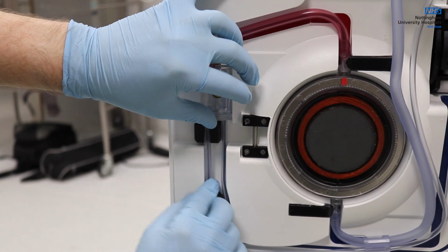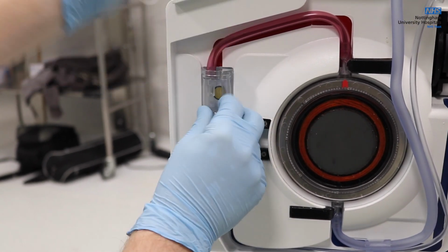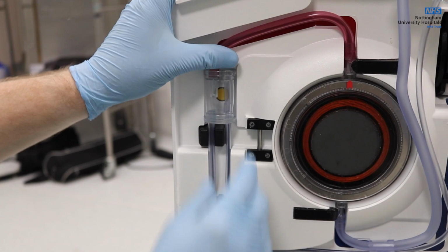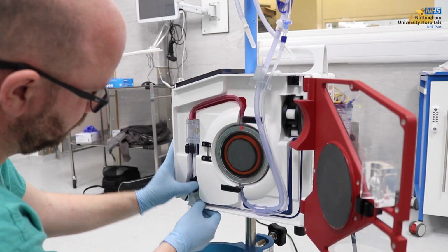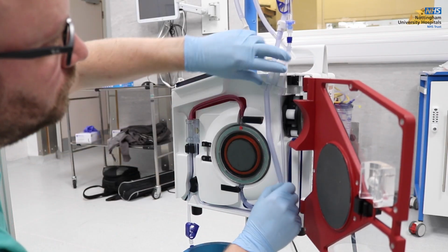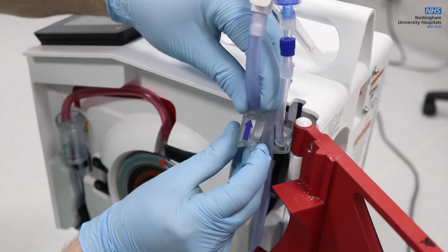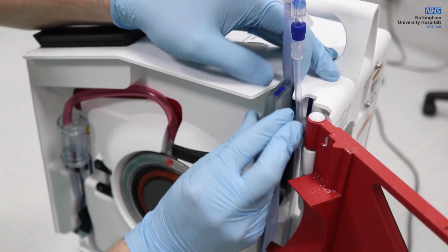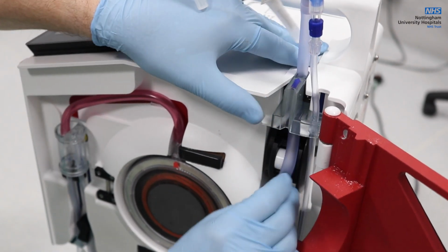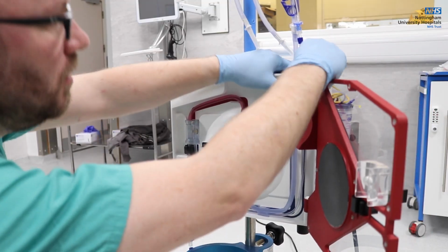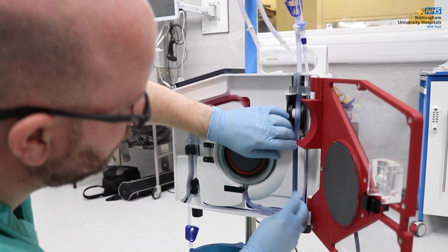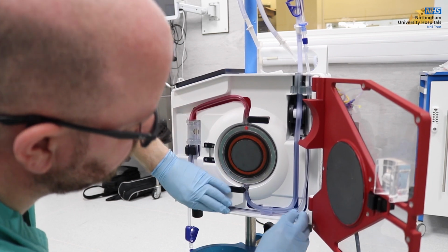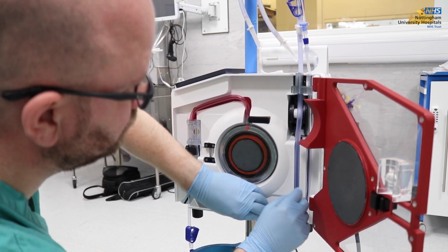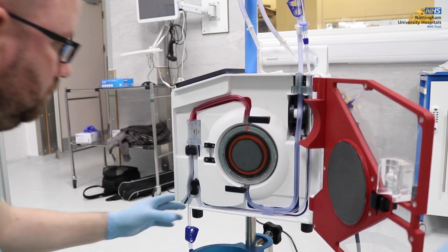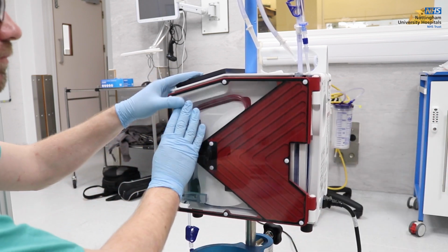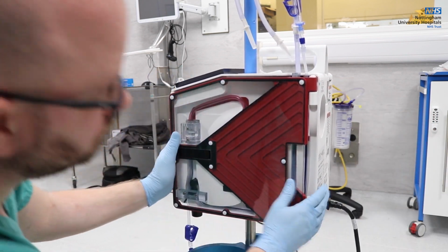Place the infused line to the left of the patient safety valve wand and place the thinner recirculation line to the right of the air detector and to the right of the valve wand. Fit the interlock block on top of the shelf. The blue arrow should be upright, pointing towards the ultrasonic air detector. Make sure the larger tubing is in the groove of the wider blue line, avoiding stretching, kinking or twisting of the tubing. The smaller tubing should be in the groove of the thinner blue line. Finally, close and latch the door, making certain the pump tubing is not caught.